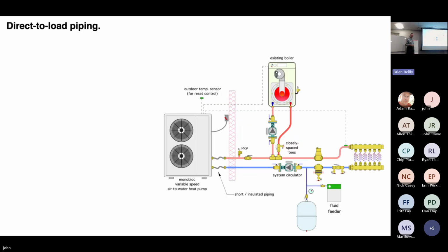Now, there are some companies that are promoting what's called direct to load piping. There's no buffer tank in the system. They're doing that because they have a wide range of speed control on the compressor out here. The idea is this. You can do zoning out here if you want, turn zones on and off, and the heat pump will sense when that happens.